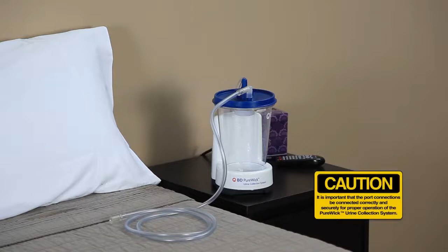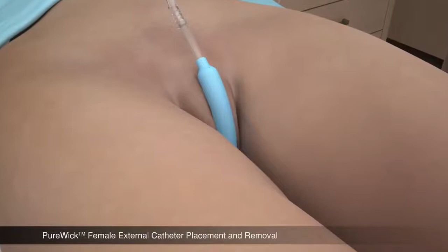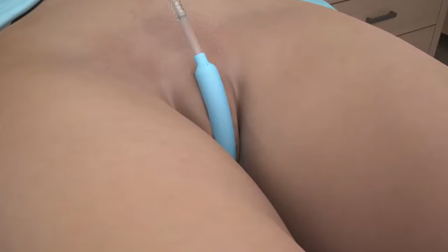Caution: it is important that the port connections be connected correctly and securely for proper operation of the PureWick Urine Collection System. Turn on the PureWick Urine Collection System by pressing the on-off switch. The PureWick Urine Collection System is working when the switch lights up green and the device makes a soft humming sound. The system is now ready for use. PureWick Female External Catheter Placement and Removal. The PureWick Female External Catheter may be positioned while the individual is laying on their back or their side.